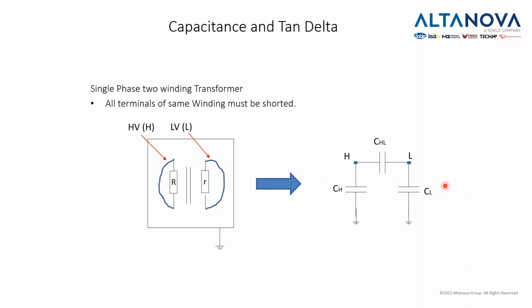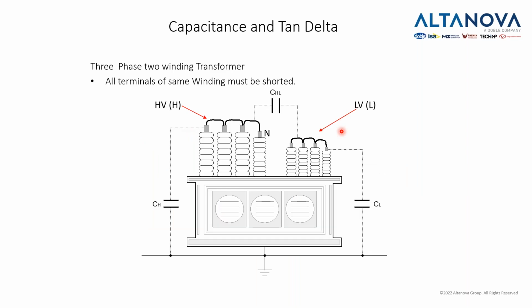And what we measure are basically on the body 3 capacitances: CH, capacitance between high voltage winding and the ground, and CL, capacitance between the low voltage winding and the ground, as well as the capacitance between high voltage and low voltage winding, CHL. While we measure capacitance, at the same time we measure this phase shift between the voltage which we generate and the current, which is generated by our voltage, and that defines the tan delta or power factor.